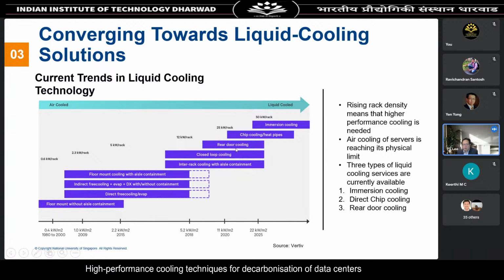Rear door cooling, also known as rear door heat exchanger, basically involves piping the liquid all the way to the rear of the rack, where you do a localized heat exchange. This ensures more uniform airflow distribution across the rack, allowing you to manage the heat coming from the different servers installed inside the rack.